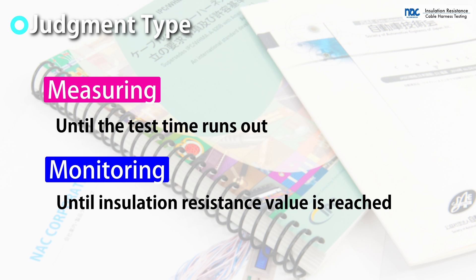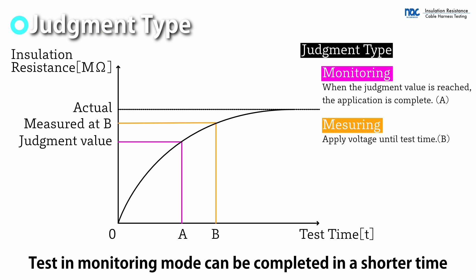In the measuring mode, the application continues until the test time is up. In the monitoring mode, the application stops when the insulation resistance exceeds the determined value and shifts to the next application. Therefore, with the monitoring mode, the test can be completed in a shorter time.